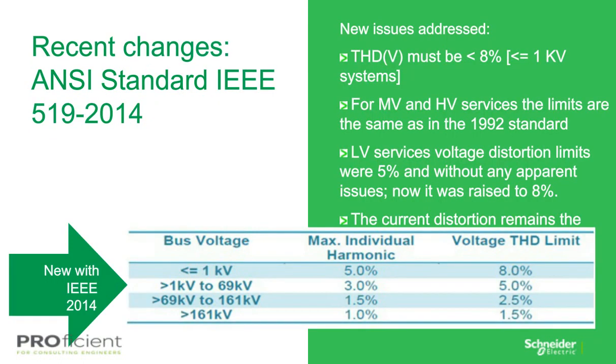So, moving on to some of the recent changes to IEEE 519, as recent as just last year, 2014. The standard dating back roughly 20 plus years was used, and what this really addressed was distortion levels below 1 kV. THDV must be less than 8% on a system of less than or equal to 1 kV. For medium voltage and high voltage services, the limits are the same as the 1992 standard. Low voltage service voltage distortion limits were 5%, and those are now raised to 8%. And the current distortion remains the same as in IEEE 519 1992.